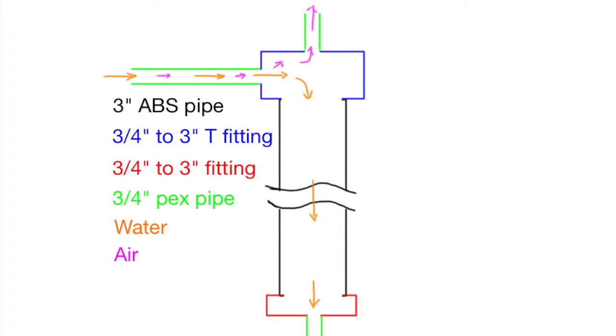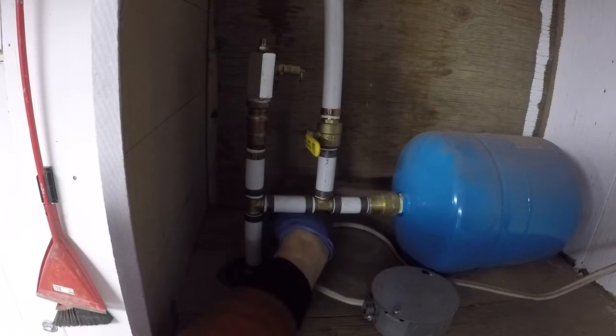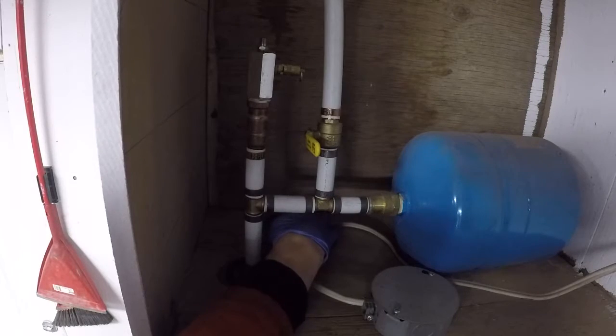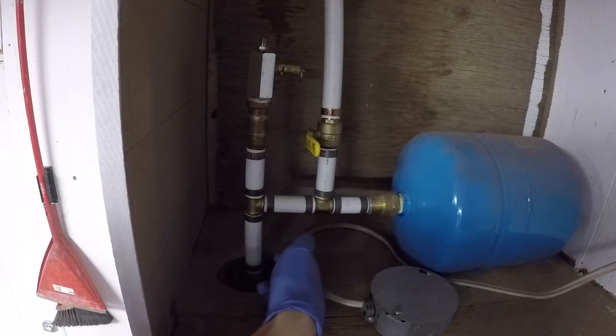So the two reasons why the air separator works so well is because, one, it's 3 feet long and you'd be trying to push a bubble 3 feet down. And the other thing is because the speed of the water in this tube is very, very slow. Because this column of water is so large, it moves very slowly. And so those two things mean that any air that enters at the top of this is going to stay at the top of this. So the 3/4 inch line comes in just below this shelf, and it comes into a T into the side of this 3-inch ABS pipe.